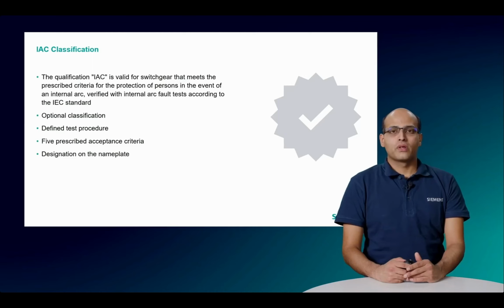As the next topic, we will focus on the IAC classification in detail. IAC stands for Internal Arc Classification. The IAC classification is valid for switchgears which meet the prescribed criteria for protection of persons in the event of an internal arc. This is verified with internal arc fault test performed according to IEC standards.